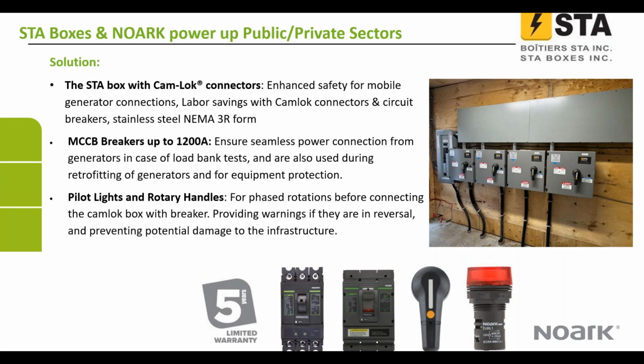Thank you. So STA boxes can be installed outside or inside. They have different finishes available, like stainless steel, steel painted gray, and aluminum. The circuit breaker adds security during the load bank test. So when the breaker is in the off position, there is no more power at the Cam-Lok connector. And our design offers a double door, so there's no possibility to disconnect the connector during a test. That is very important for us.